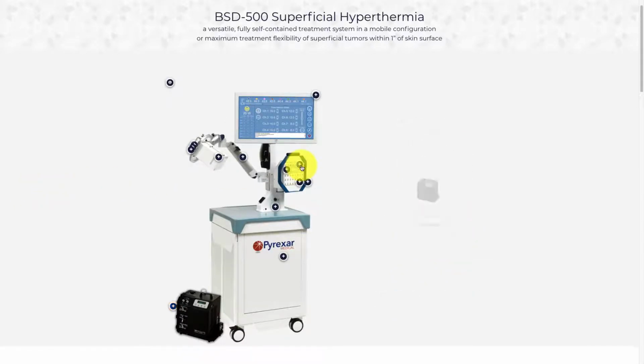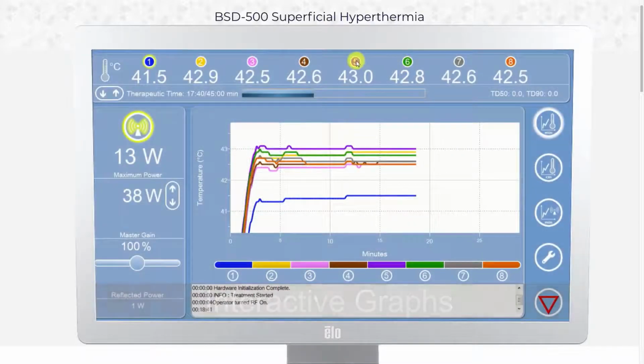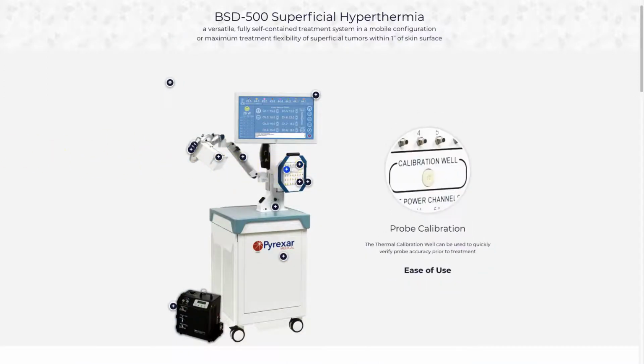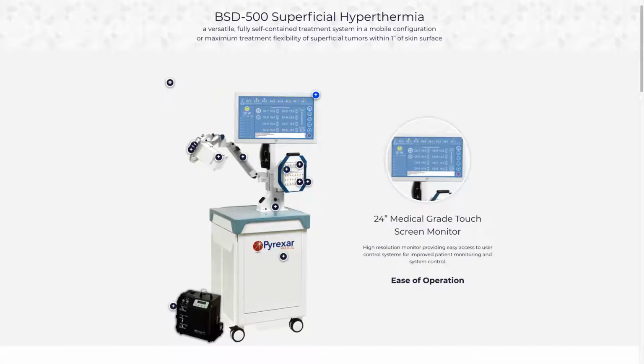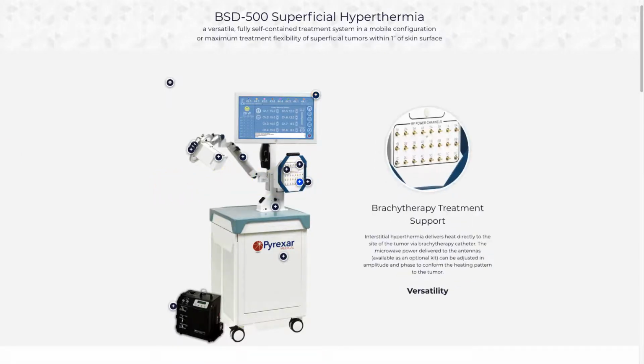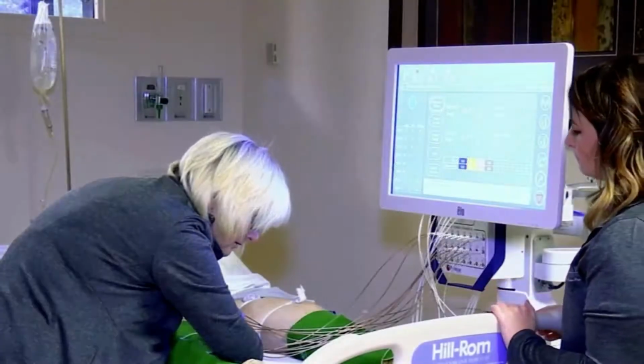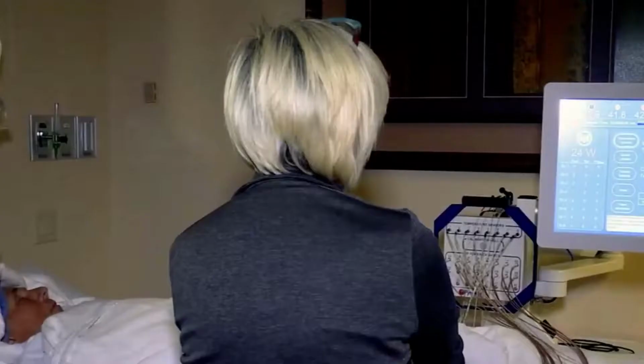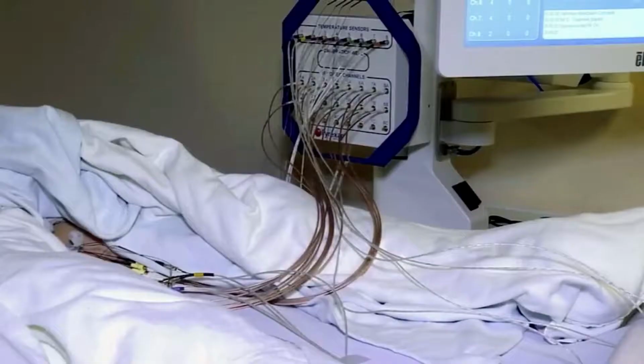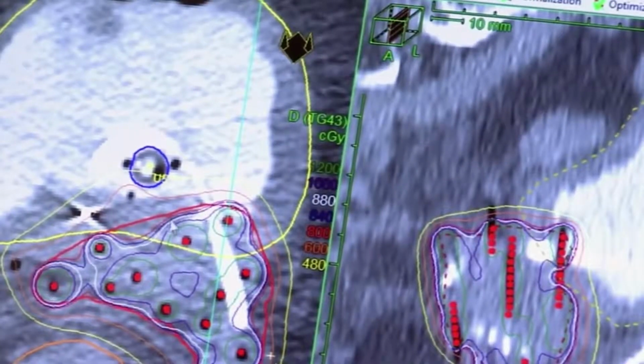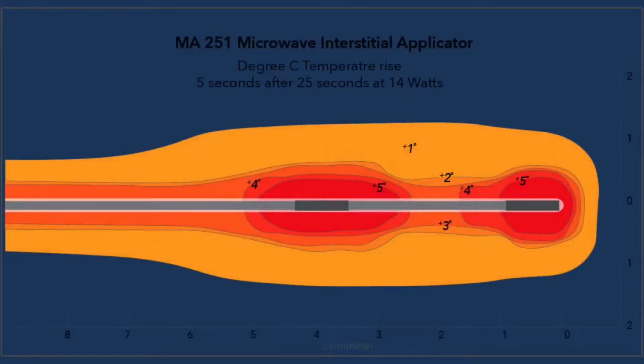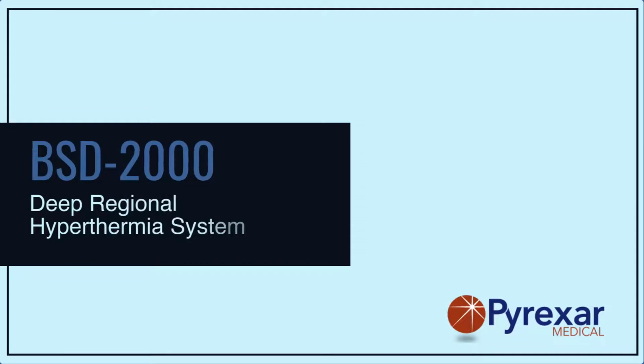The system features the ability to track up to 8 independent temperature probes for accurate thermal dosing, and an integrated thermal calibration well that can quickly verify probe accuracy prior to treatment. The user interface is controlled by a 24-inch medical-grade touchscreen monitor for improved patient monitoring and system control. One very unique feature is our support for HDR brachytherapy. Interstitial hyperthermia delivered directly to the tumor site via needle catheters placed for radiation treatment. The microwave power delivered to these antennas can be adjusted in amplitude and phase to control the heating pattern to the tumor. The BSD-2000 Deep Regional Hyperthermia System.